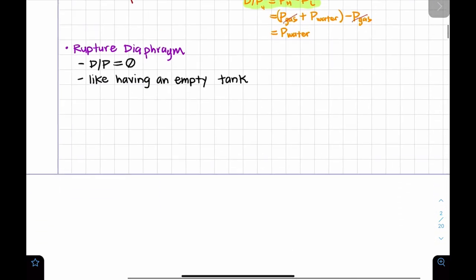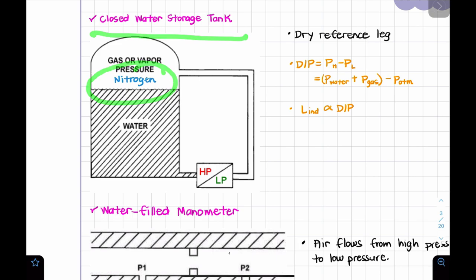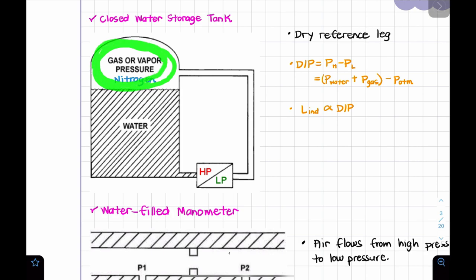The next topic is a closed water storage tank — just one problem. They ask which part is connected to the low pressure side of the detector. The tank has nitrogen or another gas inside. Remember: if you have a system with gas, the low pressure side of the detector will be on the dry reference leg — which is the gas space at the top of the tank.